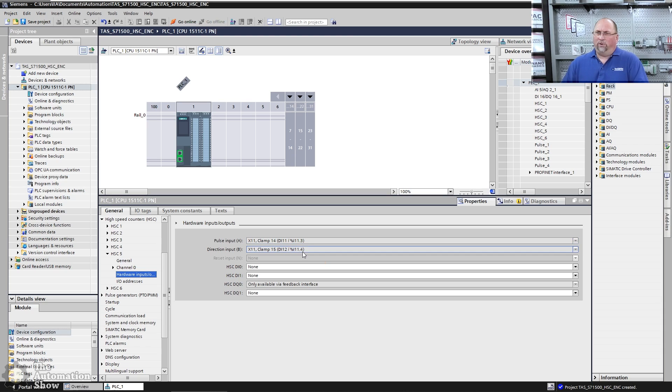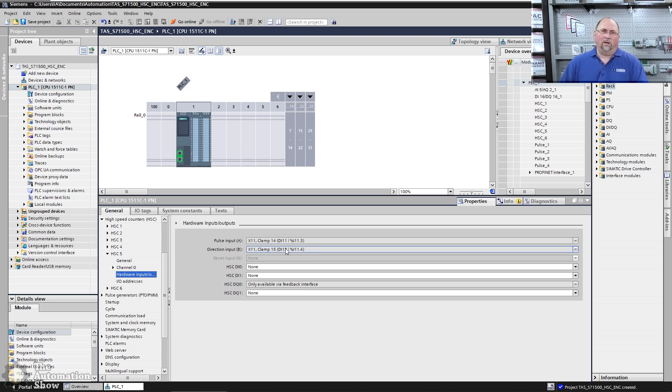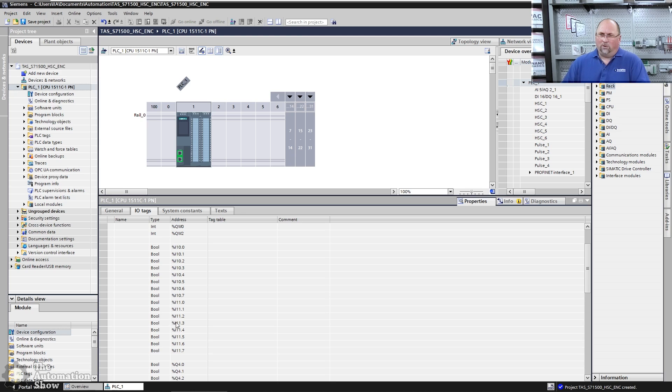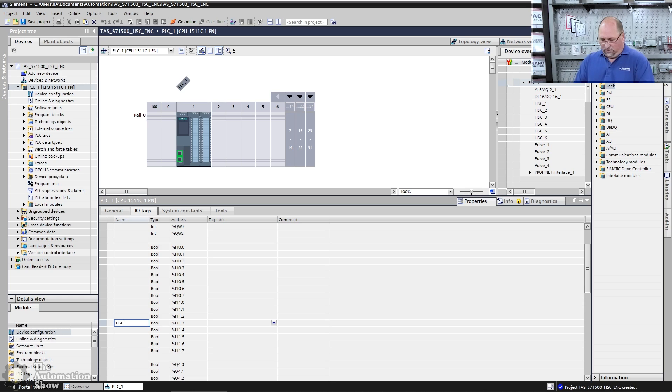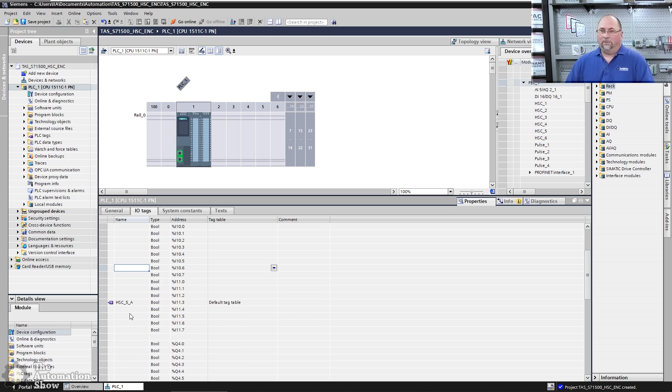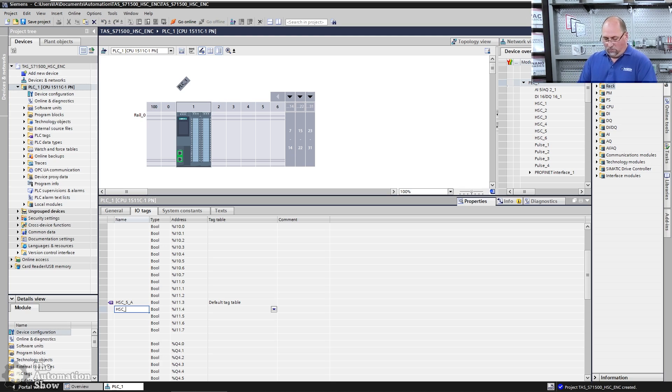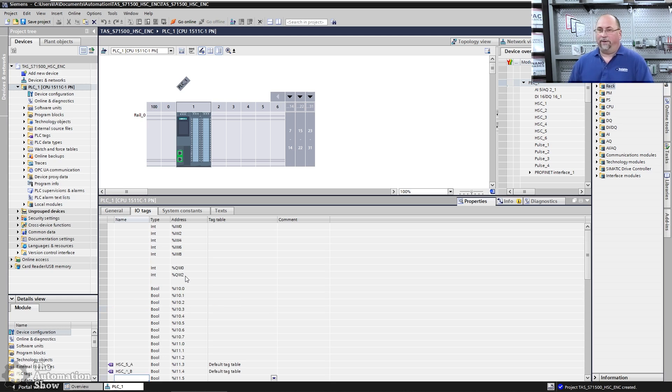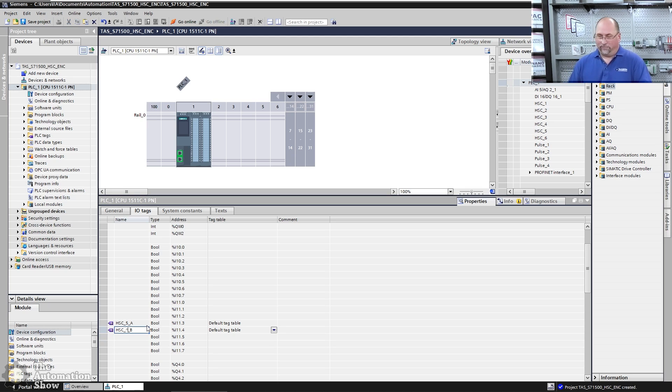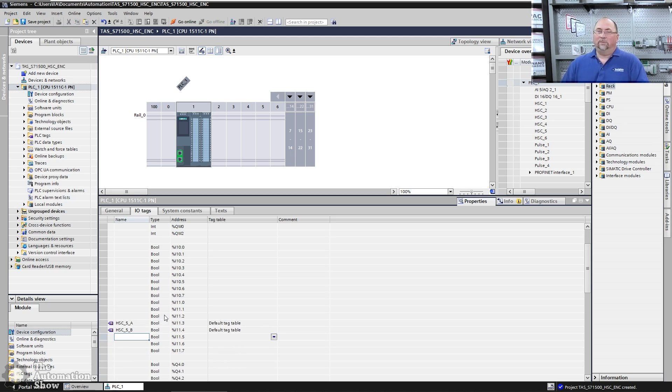If we come down here to the hardware input outputs, you can see here 11, 3, 11, 4, or 11 and 12, right? So three and four, those were the actual points on the IO card. And if you count all 16 together, they're 11 and 12. So that matches up nicely with what we saw in the field. And we can go ahead and let's document these here. So three would have been HSC five A, that's my A for my encoder. And this one is HSC_5_B. So three and four, A and B.